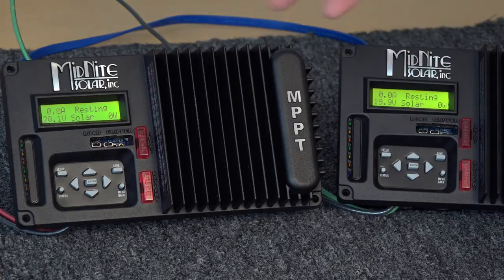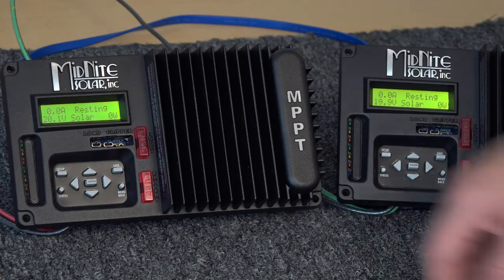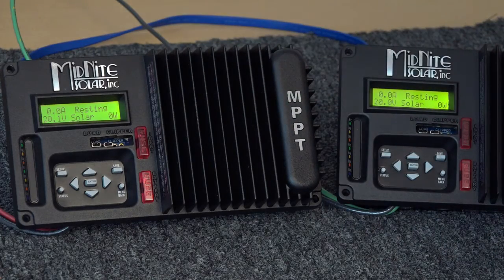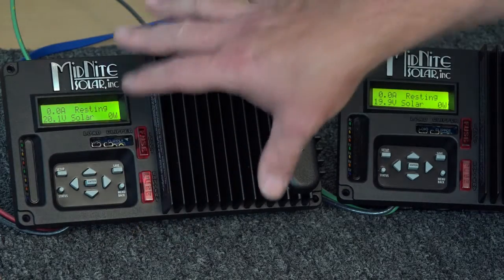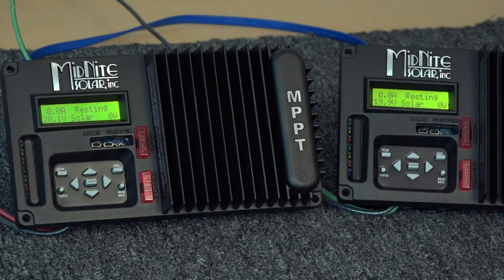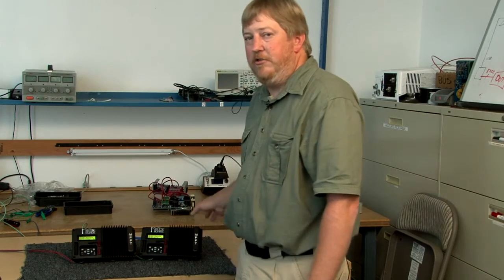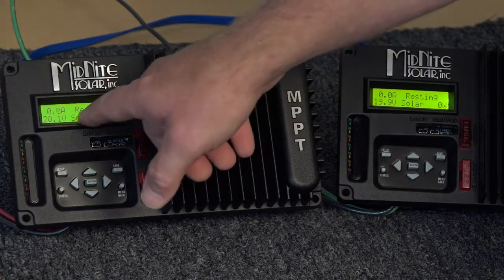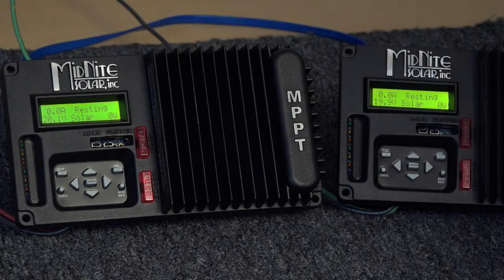It's just a nice little mode. It coordinates everybody. It gets everybody doing the same thing. The battery temperature will compensate down through. And basically what's happening is this one is doing all the brains of the work. And even if you don't calibrate the battery voltage on the other kids, this kid is going to tell them what to charge to. So if we had PV hooked up to this, solar panels hooked up to this, these would wake up. And you'd notice these would all match. Because this one is telling everybody else what to do.